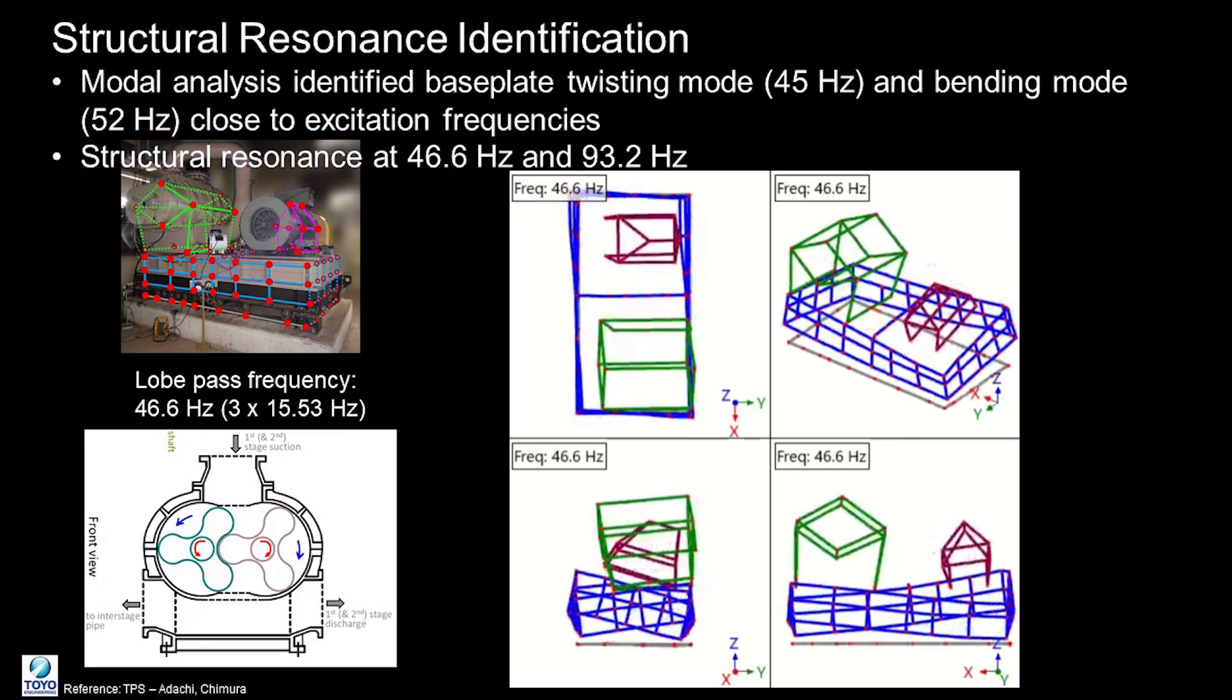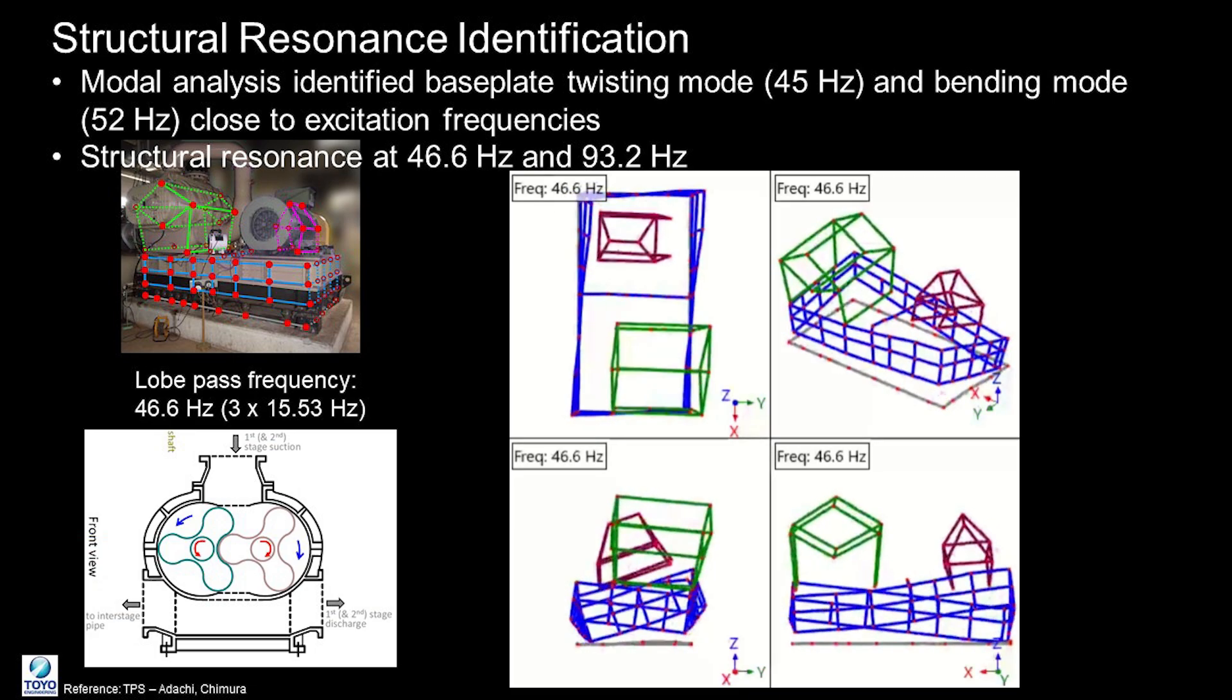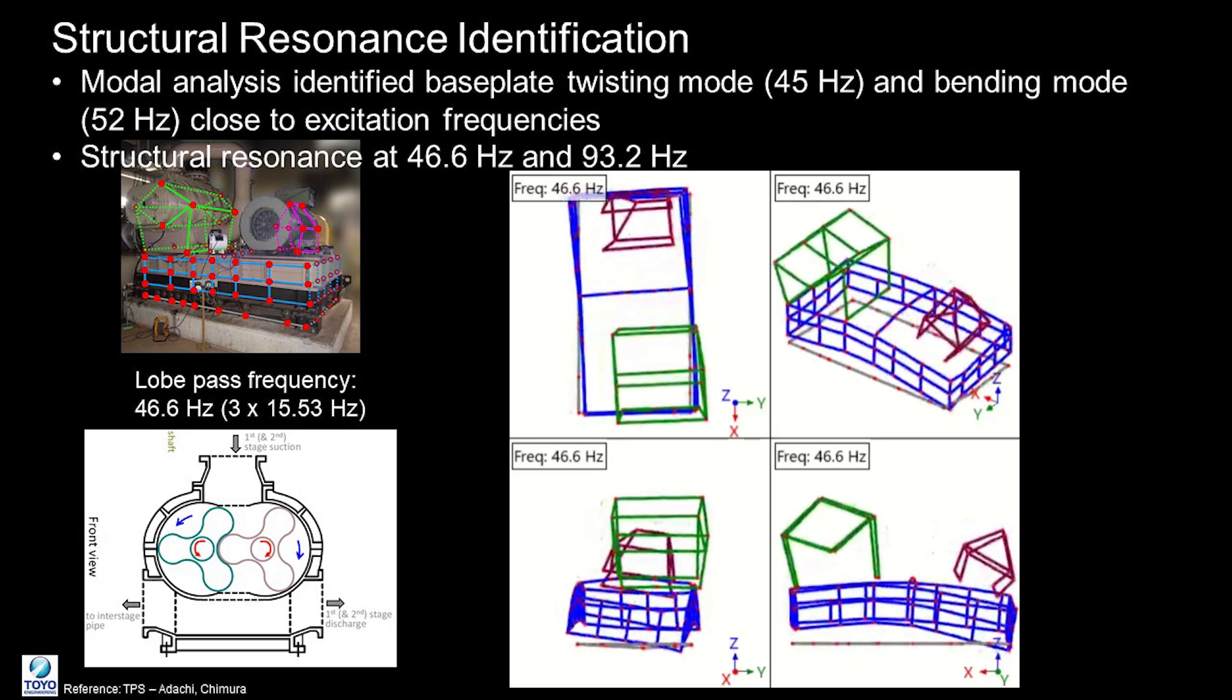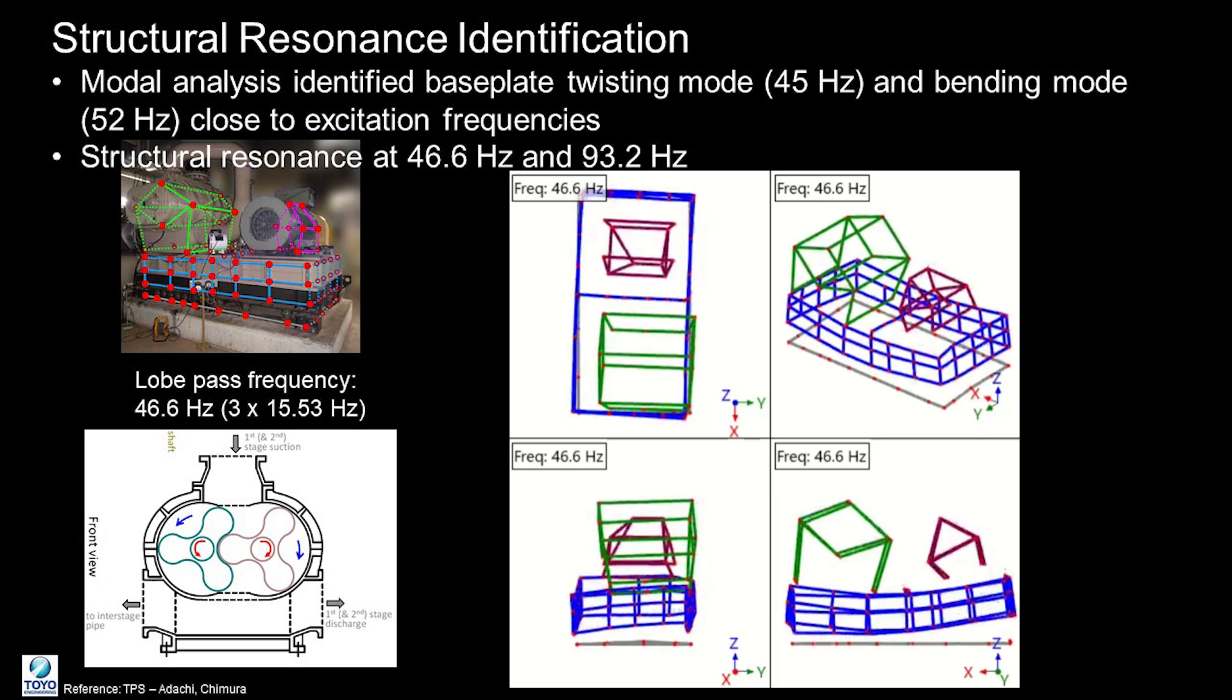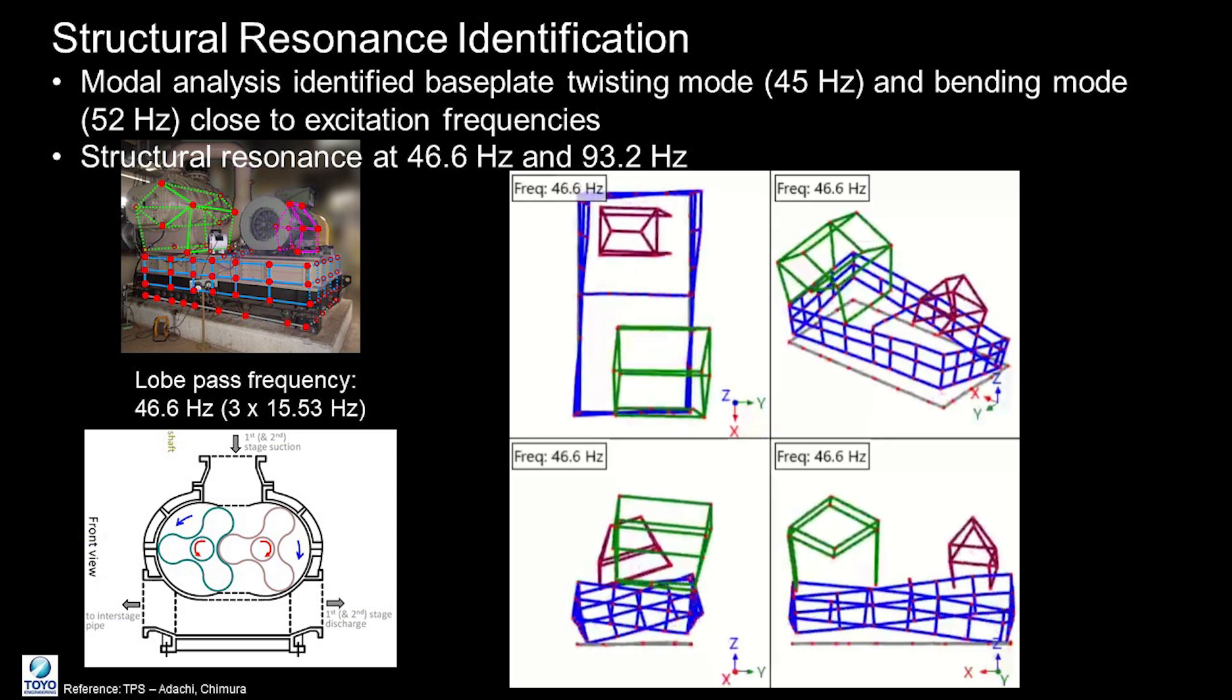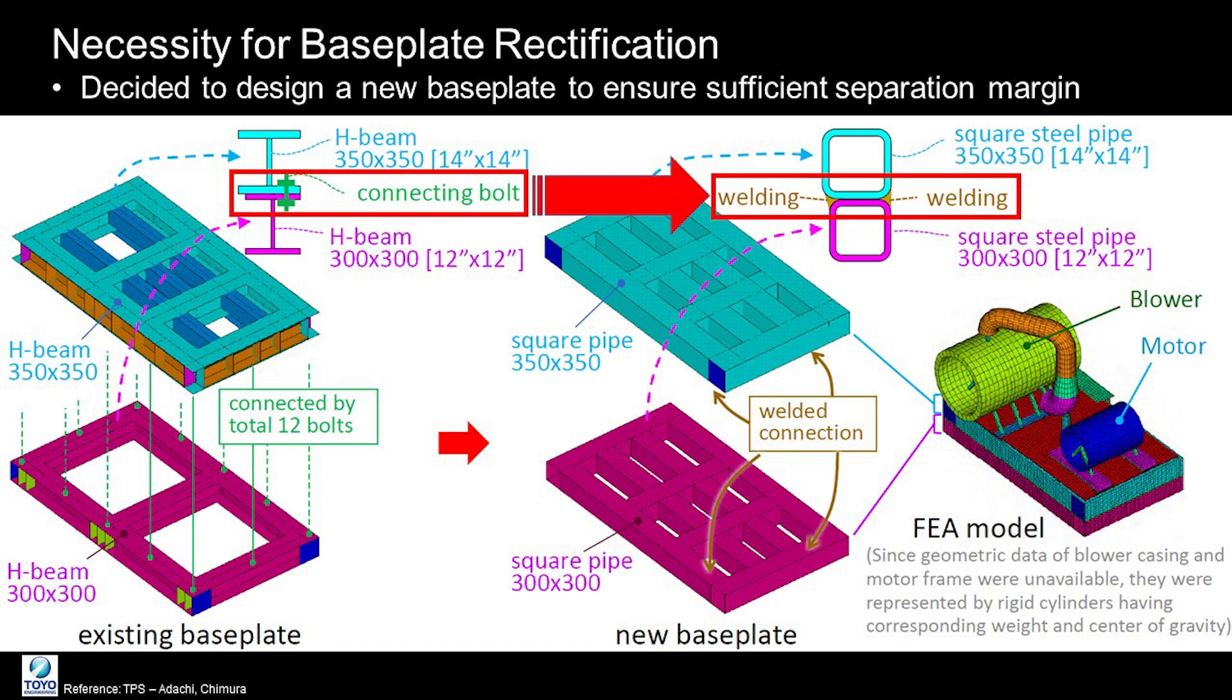Through experimental modal analysis, the structural natural frequencies were identified, and they were dangerously close to the excitation frequencies. For example, the base plate twisting mode at 45 Hz was only 3.4% away from the lobe passing frequency of 46 Hz, and the bending mode was also close. Given these findings, it was determined that the base plate needed rectification to avoid resonance.